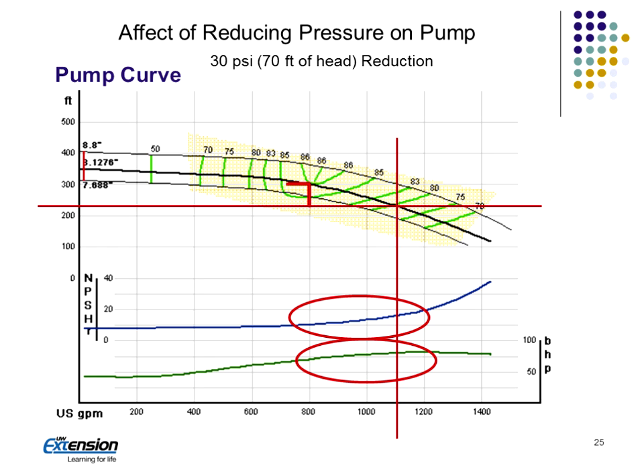So this graph is trying to show, this is a pump curve, and trying to show the effect that reducing the water pressure has. So this point here was the design point. So it's 800 gallons a minute at 300 feet of head. If we reduce that by 30 psi or 70 feet of head, there's 2.3 feet of head per psi. So we're going on 70, so we drop this down to basically 230 feet of head. And if we come over to where we intersect this line, this represents the pump curve for a particular size impeller. If we do nothing with the pump but reduce the pressure, it's going to increase the flow rate to about 1,100 gallons per minute with this particular pump.